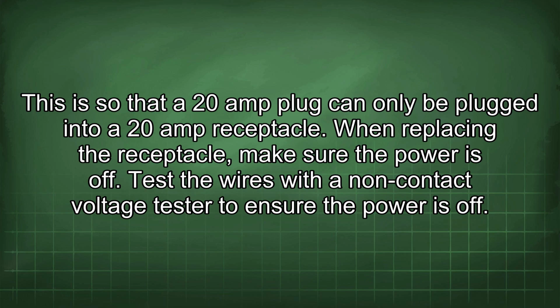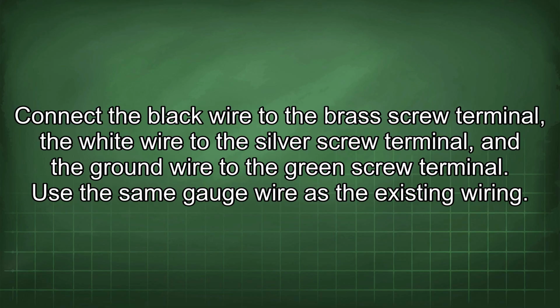When replacing the receptacle, make sure the power is off. Test the wires with a non-contact voltage tester to ensure the power is off. Connect the black wire to the brass screw terminal, the white wire to the silver screw terminal, and the ground wire to the green screw terminal. Use the same gauge wire as the existing wiring.